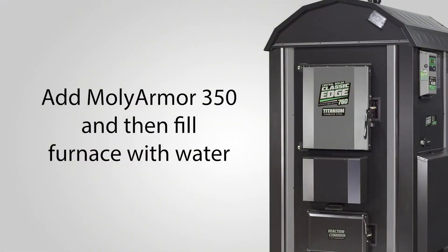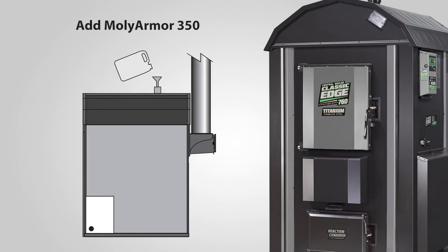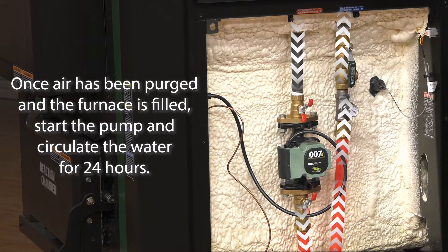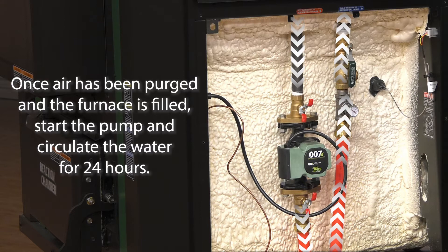Step two: add MolyArmor 350 water treatment before adding water to the system. Add the recommended amount of MolyArmor 350 through the vent pipe of the furnace. Once air has been purged from the system and the furnace is filled to one inch below the full mark on the sight gauge, start the pump and circulate the water for 24 hours.